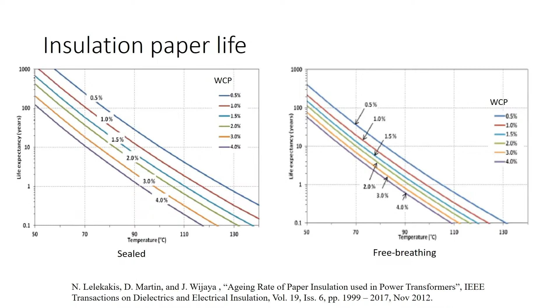As I mentioned before, roughly 6 degrees of extra temperature elevation will halve your life. If we're taking a transformer at a low load, then an extra 6 degrees won't really do that much in terms of life expectancy. However, if we're running it at a high load with a lot of customers or industry connected on a transformer, then harmonics can become more significant.